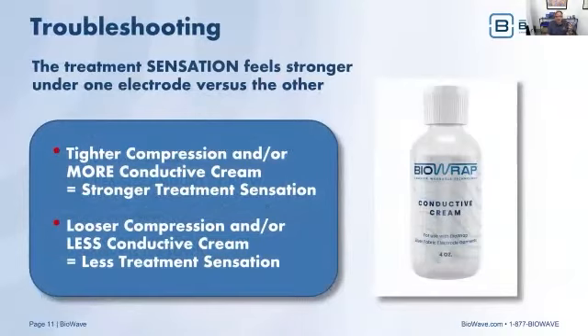So there's one other, this is less of a troubleshooting and more of a pro tip. Let's say that you're all connected and it's working, but the sensation that the patient feels is stronger under one electrode versus the other. So you have 2 variables here for controlling the sensation on either of those 2 electrodes relative to one another. The 2 variables are compression and the amount of conductive cream you use. So the tighter the compression and/or the more conductive cream that you use, the stronger the treatment sensation. The less compression, the looser the BioWrap, and/or less conductive cream will mean less of a sensation.